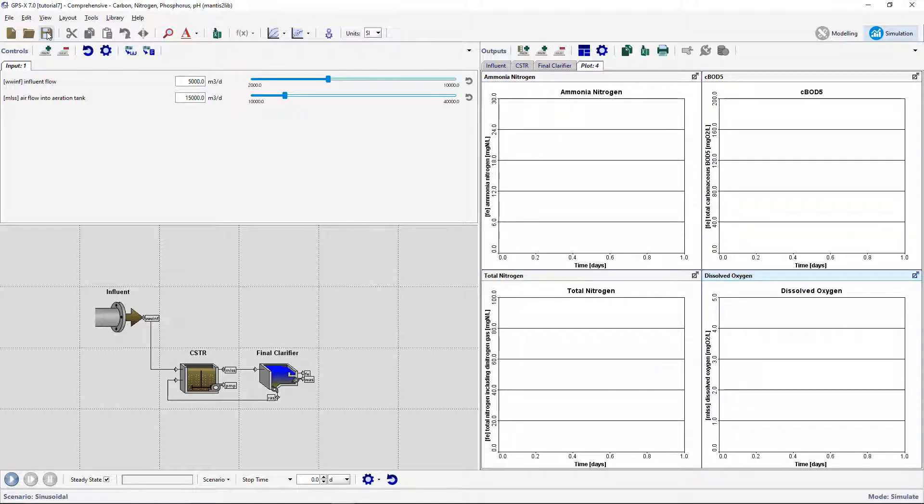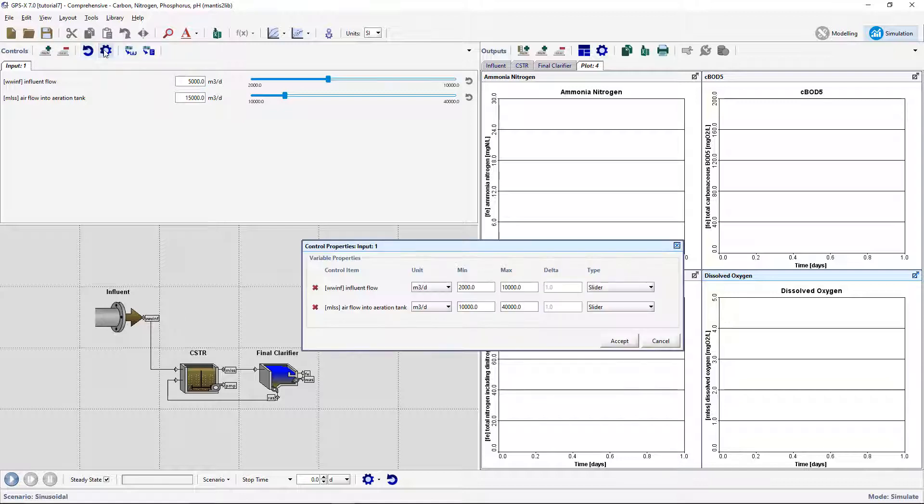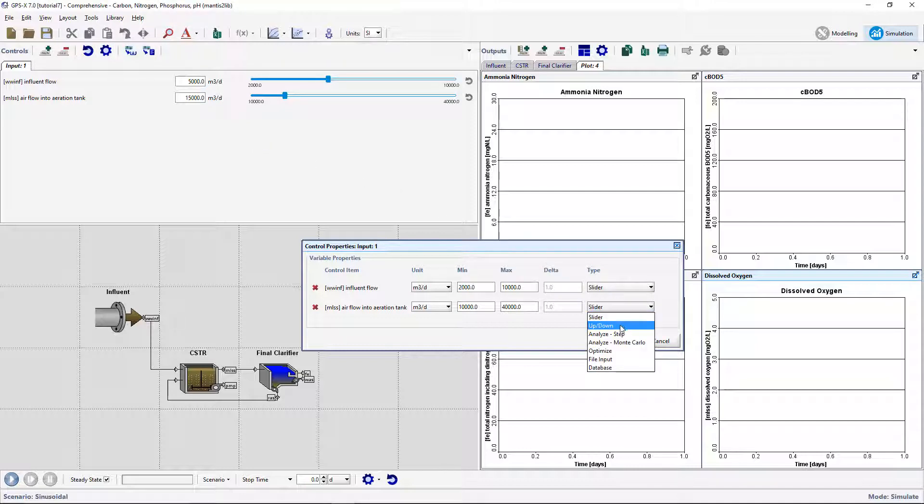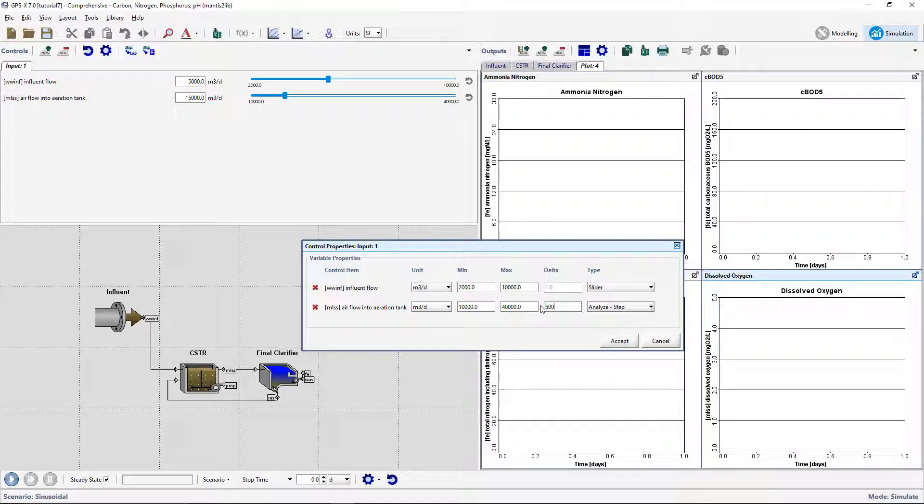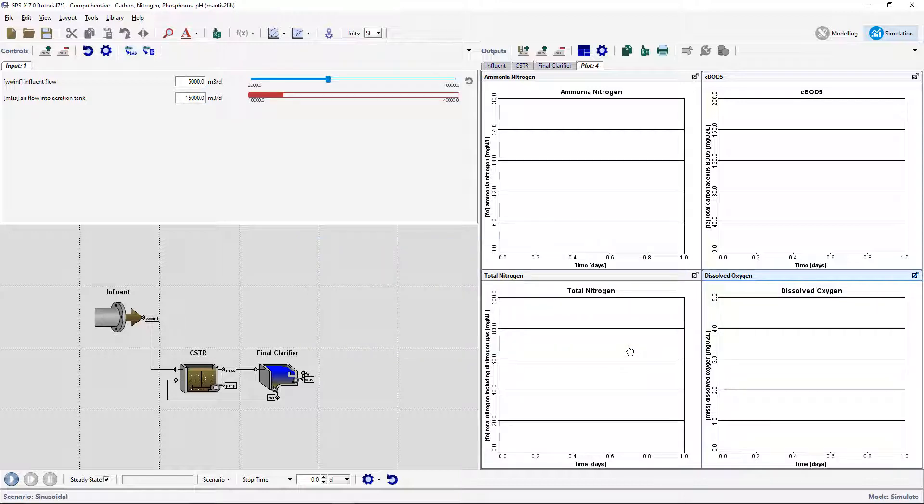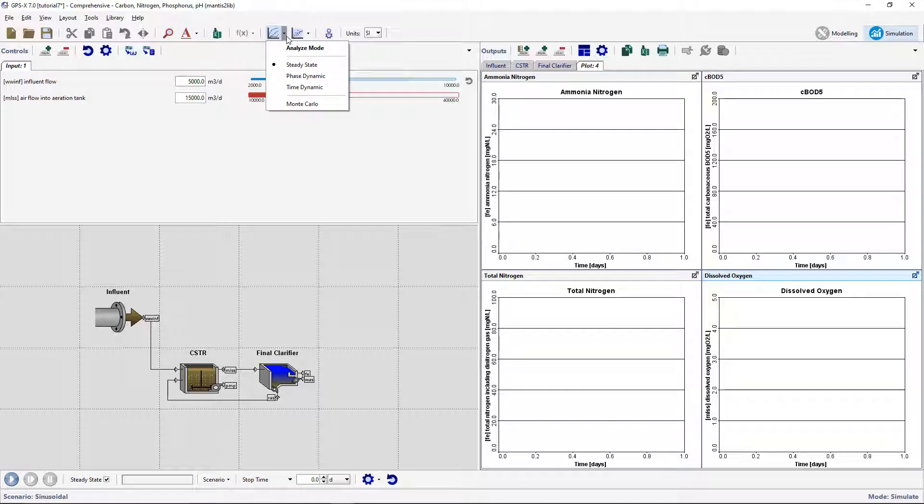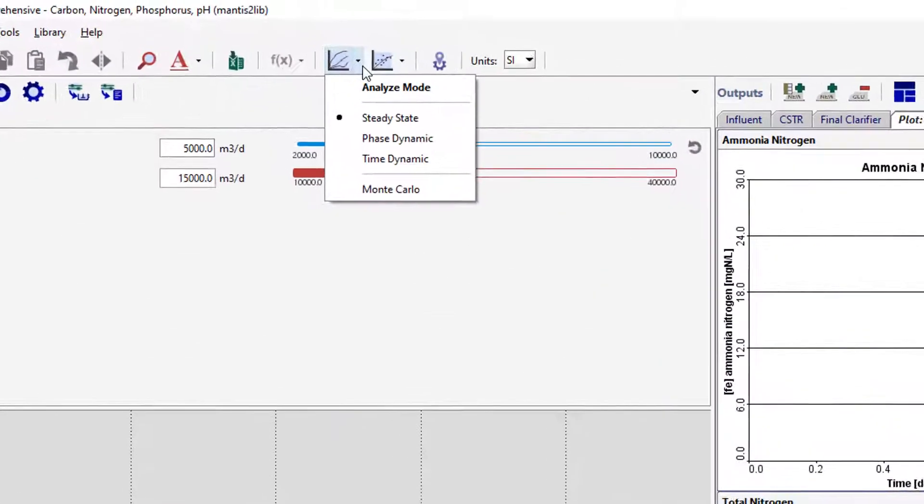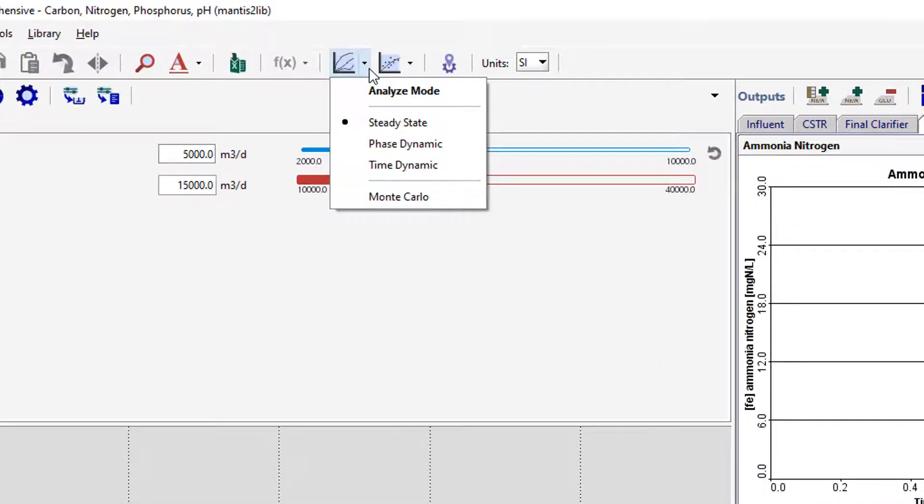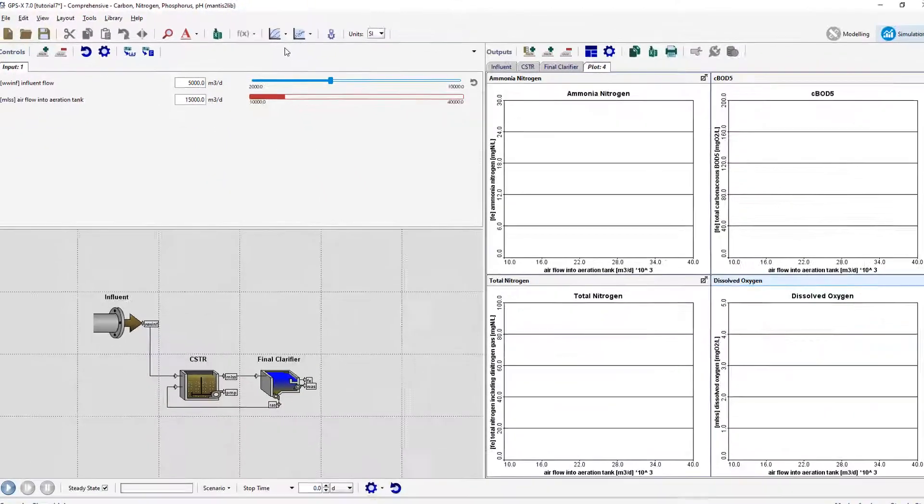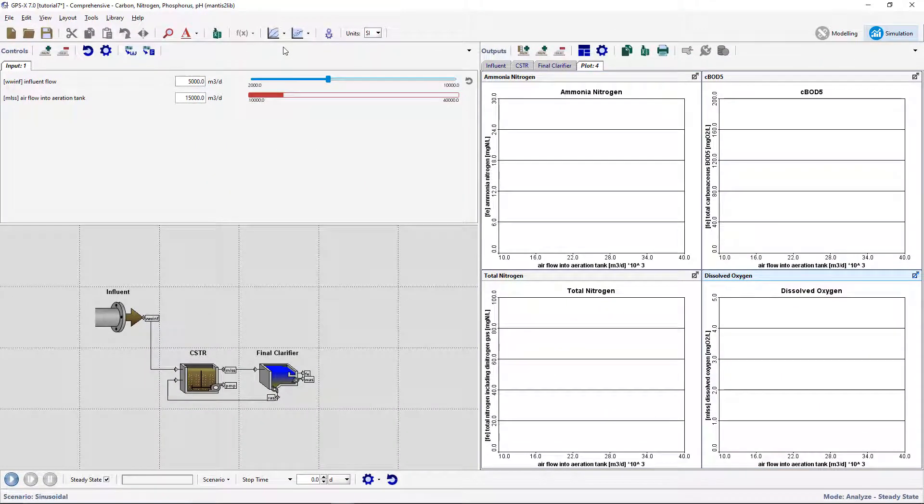We will now look at the effect of the airflow on the four dependent values that the graphs were just created for. Open the Control Properties window and change the airflow into Aeration Tank from a slider type to Analyze Step Control. Change the delta value to 500. From the main toolbar, click on the arrow beside the Analyze button and confirm that Steady State has been selected. Turn on the Analyze mode by either selecting this from the drop-down list or click directly on the Analyze button.